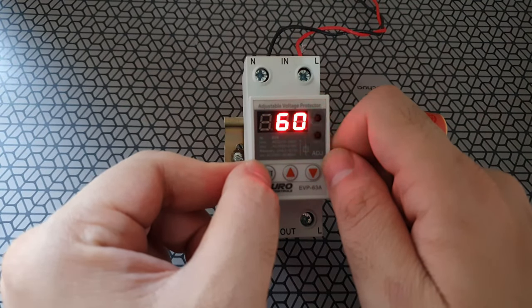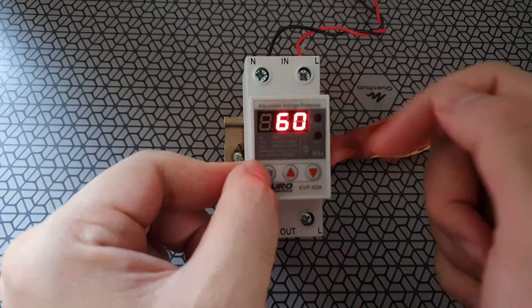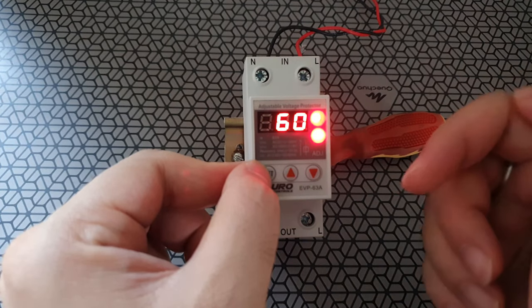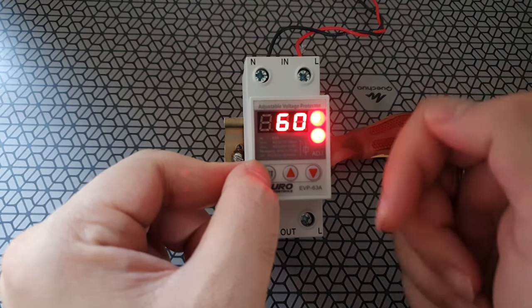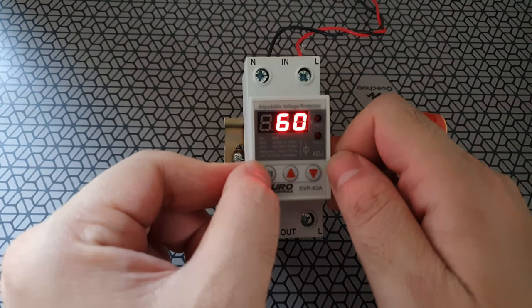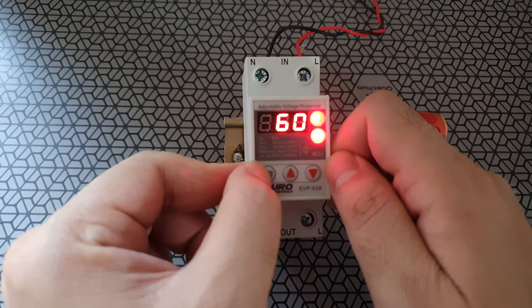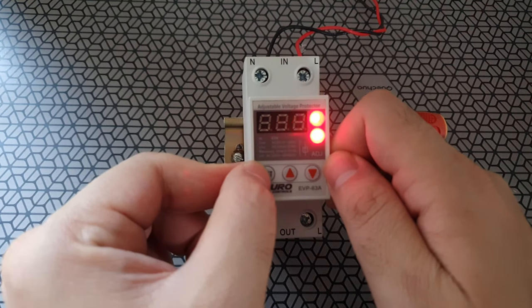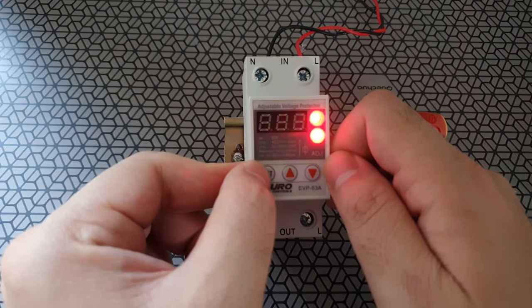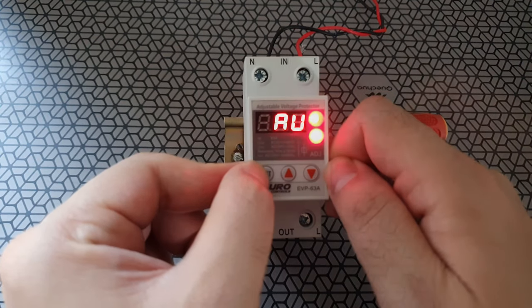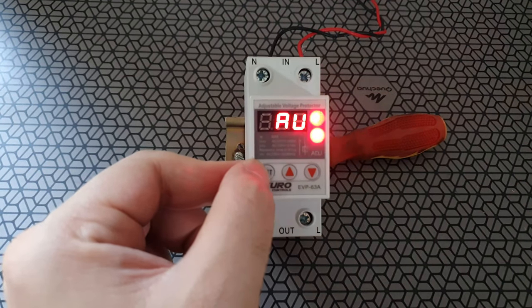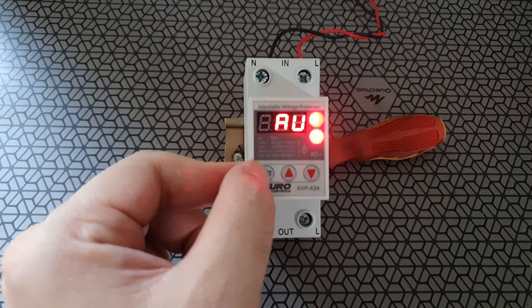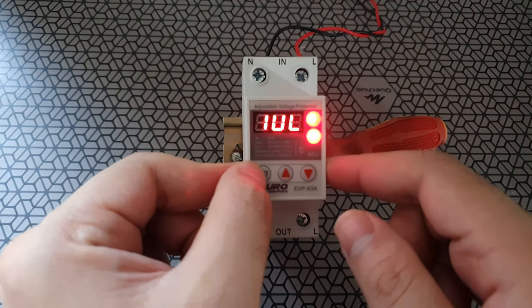So let's say there is a cutoff. So you have a default time gap of reboot, which is about 60 seconds. So once the voltage is restored, it'll take about 60 seconds to power back all your devices on. This is adjustable up to 512 seconds. So default power on time is 2 seconds. So the moment power comes into this device, it takes 2 seconds. AU represents fully automatic. That means the device is set to turn on and turn off things automatically.